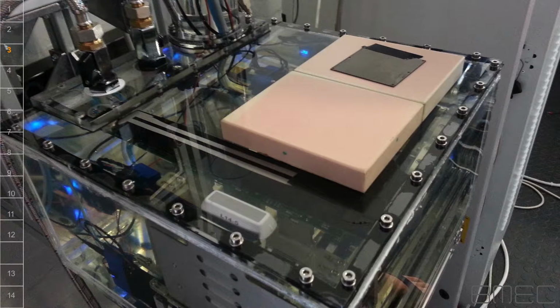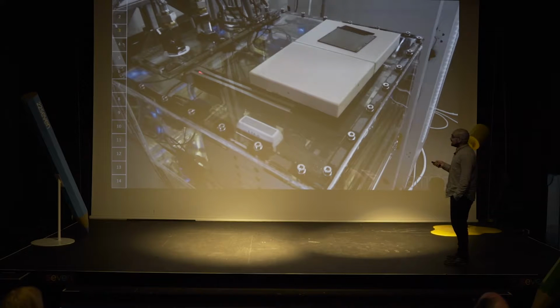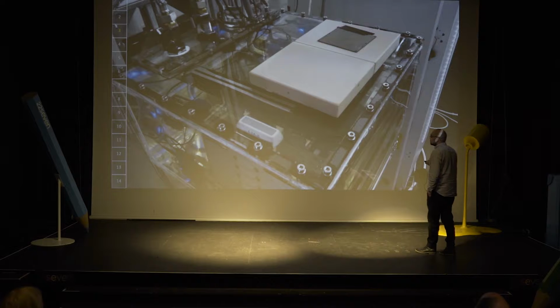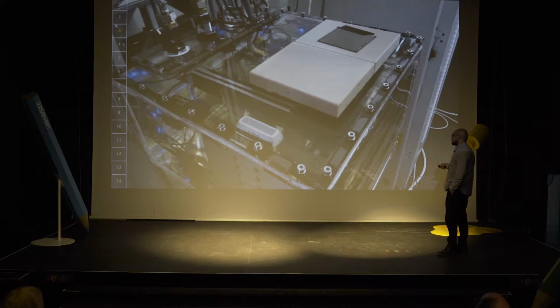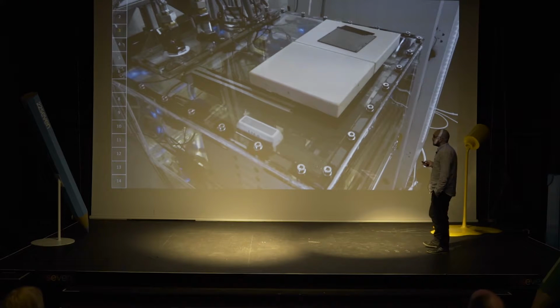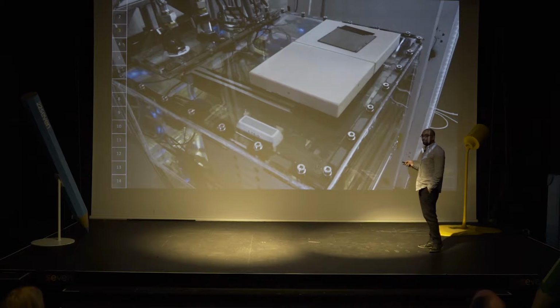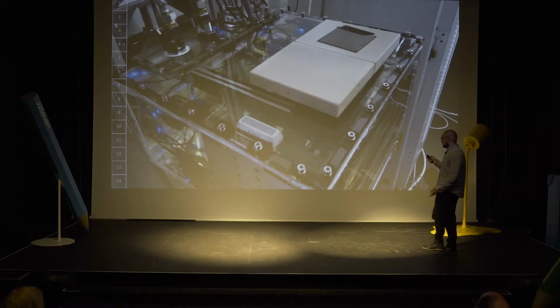Shown here is an image of our very first breast platform. This is the X-ray detector. That's the ultrasound probe. This ultrasound probe was a handheld, off-the-shelf probe. And we got relatively good images with this setup, but the ultrasound probe was only 40 millimeters long, so obviously not long enough to cater for all breast sizes. So that was our next challenge, to find a way to make this ultrasound probe longer.